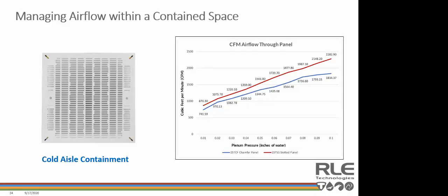At a very high level, when we're looking at the entire room, a basic rule of thumb for calculating cooling requirement is to take your available cooling tonnage and multiply it by 3.52. This will let you know how many kilowatts of IT load you should be able to safely cool. An example of this is if you have, say, 100 tons of cooling available, you should be able to cool approximately 352 kilowatts of IT load. Now, there are some caveats to this rule, such as making adjustments for altitude, restrictions within the cooling plenum, and that kind of thing. But this is a good starting point.